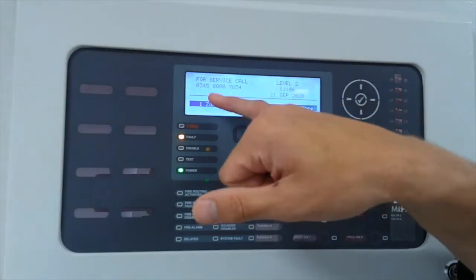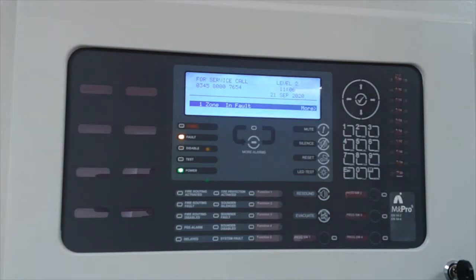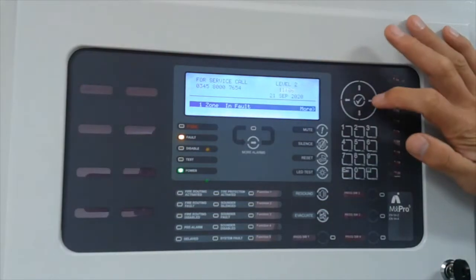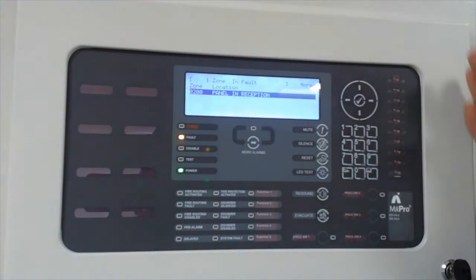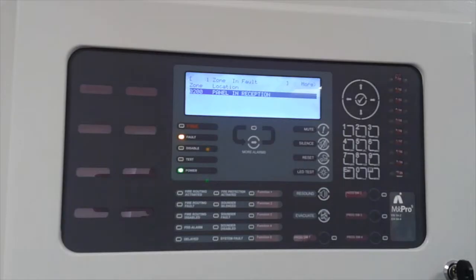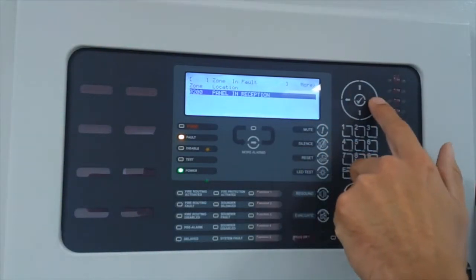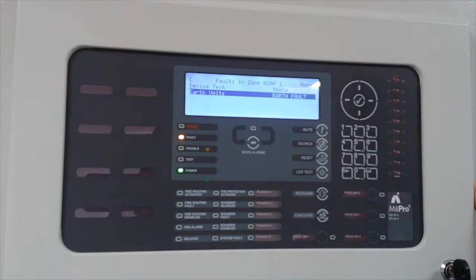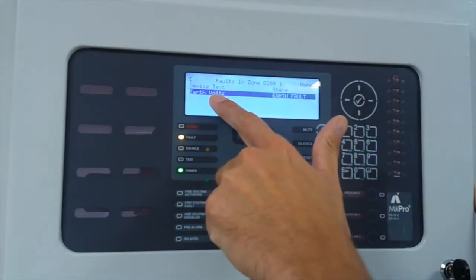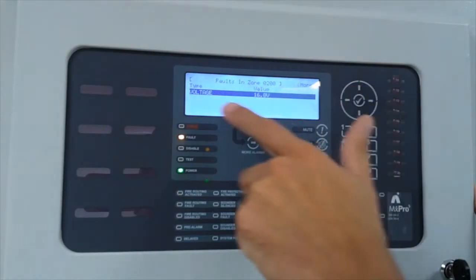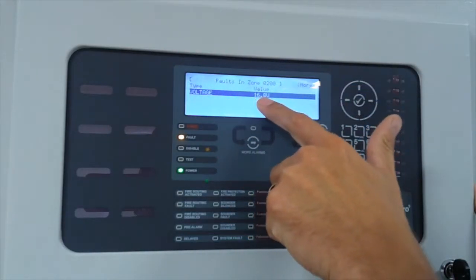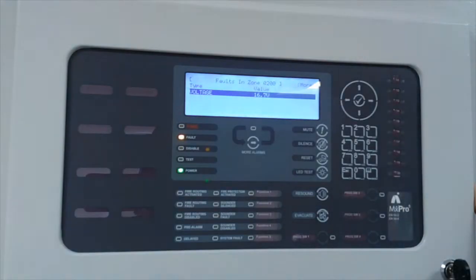The moment I press the mute button, that menu changed. If you scroll to the right hand side, one zone in fault: zone 200. Zone 200 is the location of your control panel, in this case the panel in reception. Scroll to the right for further information. We can see the device text: earth faults. The state is an earth fault, voltage is the measurement type, and our voltage measurement is 16.8 volts.